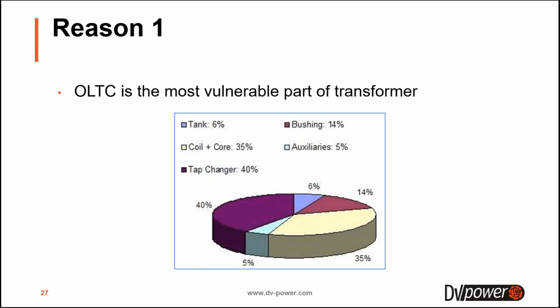But what is common for all of them is that the component in the transformer that is most prone to damages is the tap changer. In this research it was 40%, but it can be more or less. But generally, OLTC is the most vulnerable part of the transformer, and there is a simple explanation. The tap changer is the only moving mechanical part of the transformer. If we exclude oil, which is also being moved in the transformer, OLTC is the only part that is moving during operation, and because of that, it is more prone to degradation of the material, and that's why it is very important to test the OLTC.